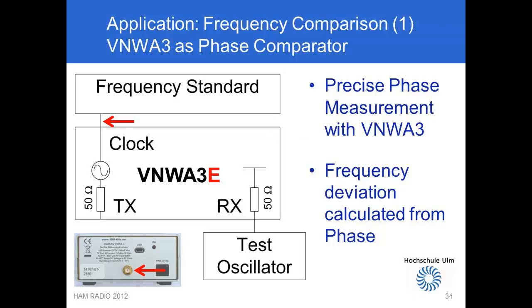Any signal test oscillator can be connected to the RX port and then measure the phase change of the test signal relative to the reference signal and subsequently calculate the frequency difference to the nominal frequency.